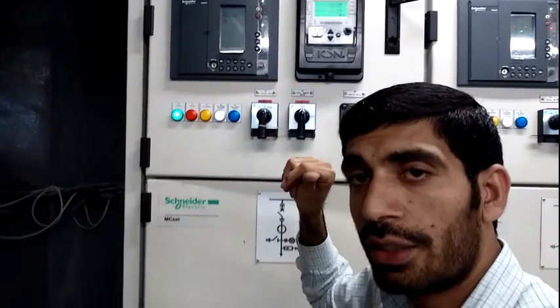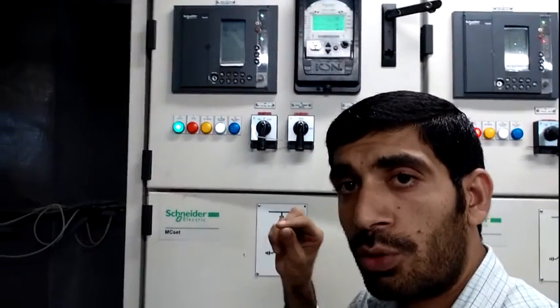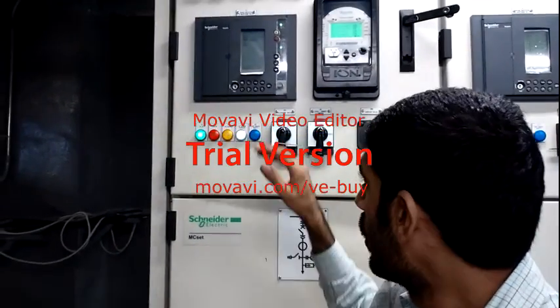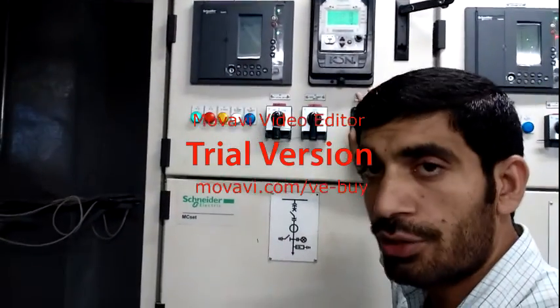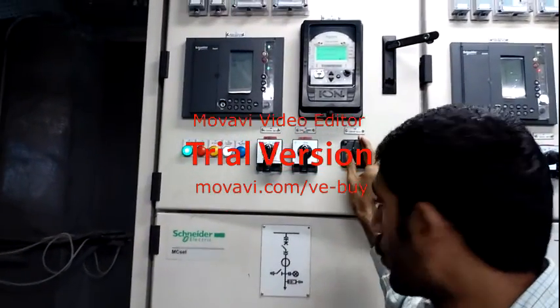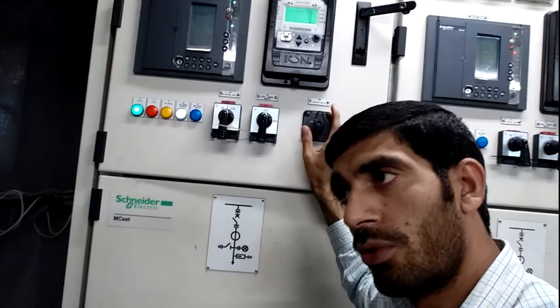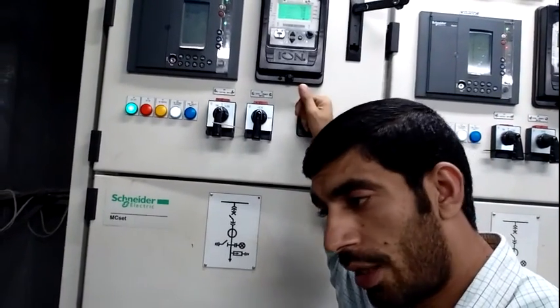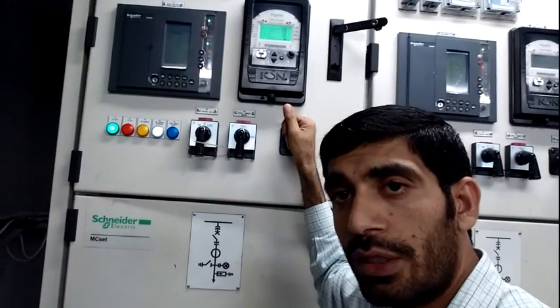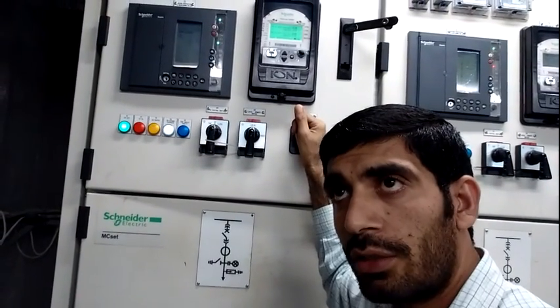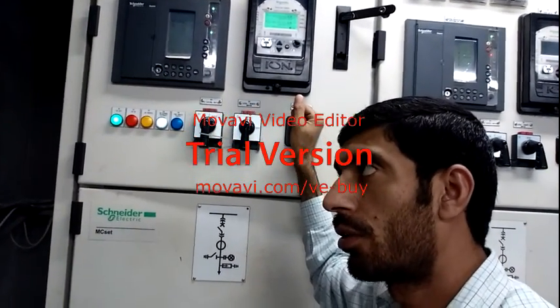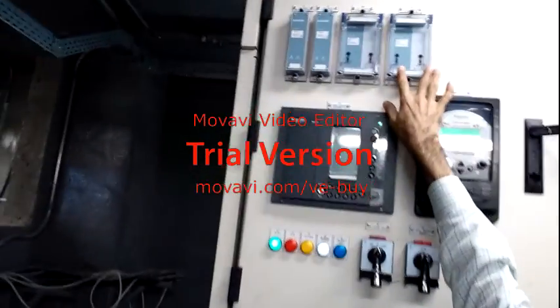In a short circuit or earth fault condition, this will trip within 200 milliseconds and show it here, and your breaker will open, and the lockout will also operate, and you cannot reclose your breaker. First of all, you must solve your problem, short circuit or earth fault, then you can reset your lockout relay and you can close your breaker. This is all the relay gives.